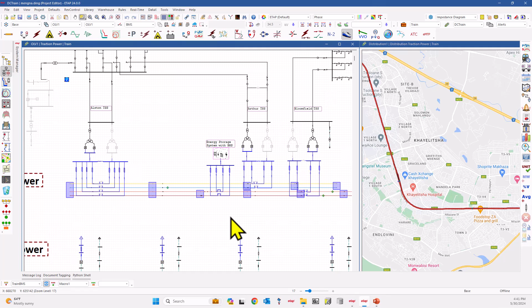Let's take this time to look at the energy storage modeling we have in ETAP. You can define the battery management systems by setting the charge and discharge logics, either with a bus voltage. You define a bus ID, and when the voltage is higher than a certain percentage, that means the system has enough regenerative power that boosted the system voltage, and then the battery can get charged. And vice versa, when the voltage gets lower, the battery starts to discharge into the system.